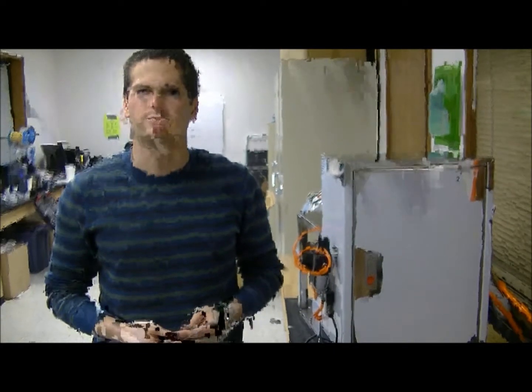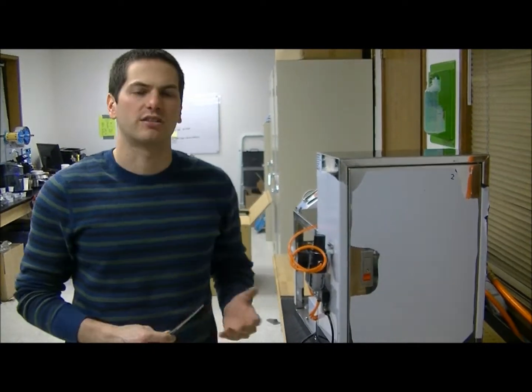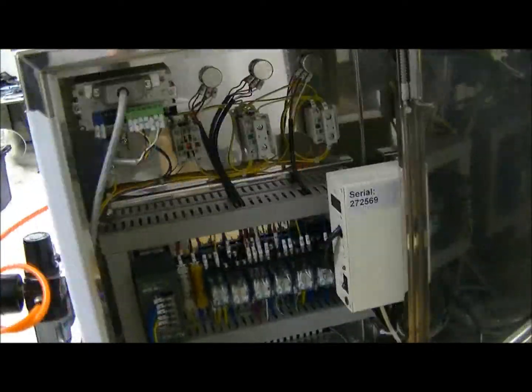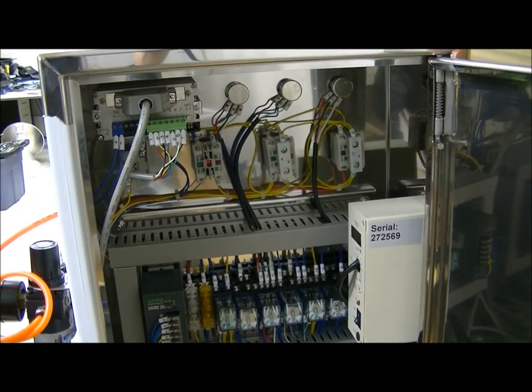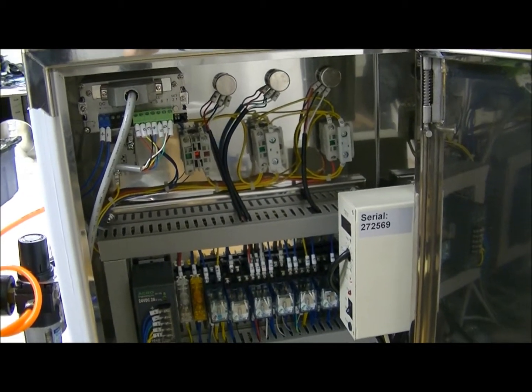Okay, and the last thing that I'm going to show you how to do here is the calibration of the machine. Much like setting the set point, this can be a little challenging the first couple times you do it. Unlike setting the set point, this isn't something that should need to be done very often. But if you have any questions, the step-by-step procedure is in the operation manual. The first thing that we're going to do is open up the back of the machine by pushing this button here, and this will open up the back to where all of the electronics are. Before working in here, make sure that the machine is turned off and unplugged just for safety reasons.